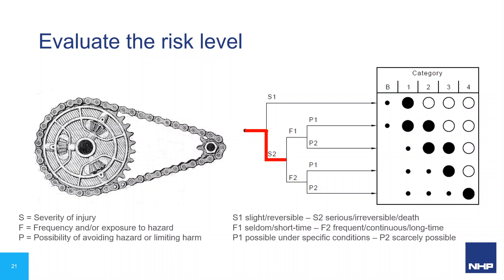We move along to F — frequency of exposure. How often is someone standing in front of this chain and sprocket? If they lubricate the chain maybe once every 6 months taking 30 seconds each time, that's seldom — F1. But if they lubricate it once per shift, 280 days per year, that's more frequent — possibly F2. In this case, let's consider F2 because maintenance is performed once per shift.